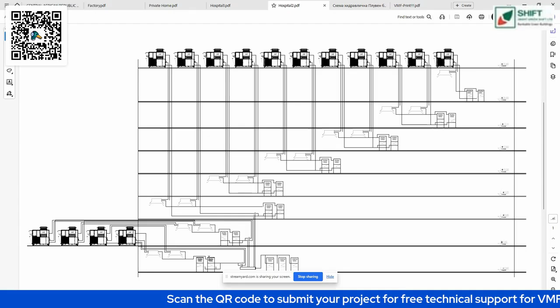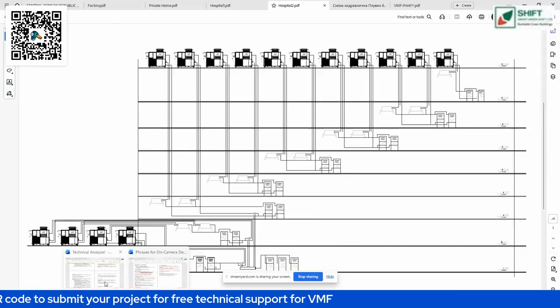The numbers for this project are even bigger. This is our comparison analysis on Bulgarian, but I will show you that the refrigerant quantity in the original design with the VRF units was over 700 kilograms. From over 700 kilograms, we go down to 230, almost 3 times less. Very important, the installed electric power input in the original design with the VRF was over 800 kilowatts, and we went down to 350, which again is more than 2 times less.